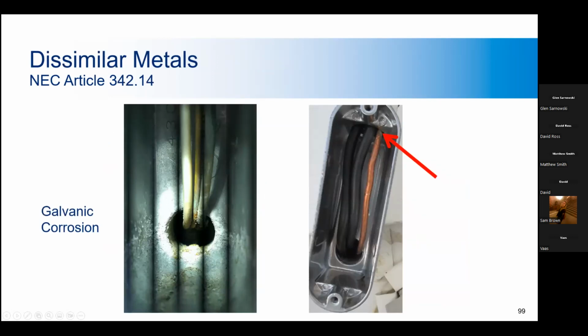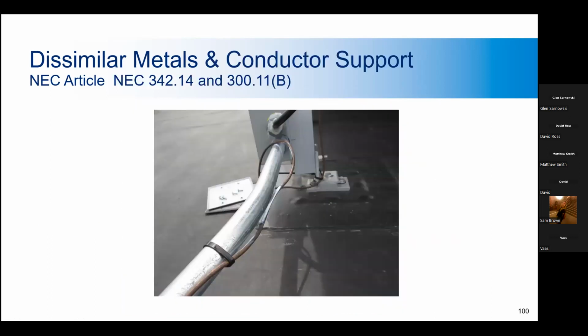Here you can see examples of galvanic corrosion. Many contractors underestimate the effects of galvanic corrosion, and that happens with the direct contact of dissimilar metals. Here are two situations where copper conductors are in contact with a dissimilar metal in a wet location, and it's clear that the conductors are quickly corroding and deteriorating. You can see it more over here, but up here you can see just the beginnings of it. A way to avoid this is to use insulated conductors, or there are other methods as well.